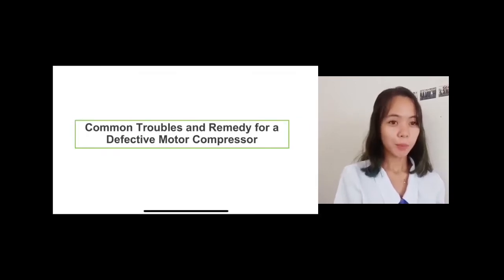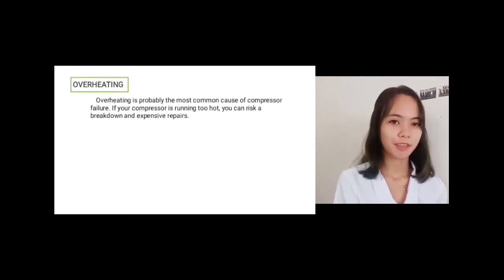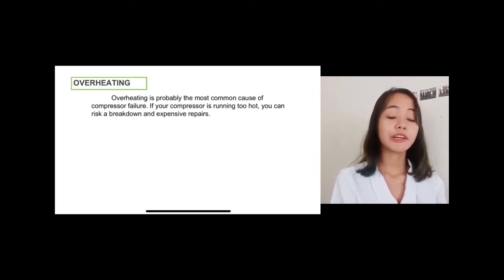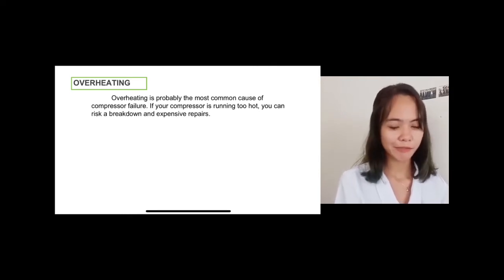Moving to the next topic, we will be tackling the common troubles and remedies for a defective motor compressor. The first trouble would be 1. Overheating. Overheating is probably the most common cause of compressor failure. If your compressor is running too hot, you can risk a breakdown or expensive repairs.